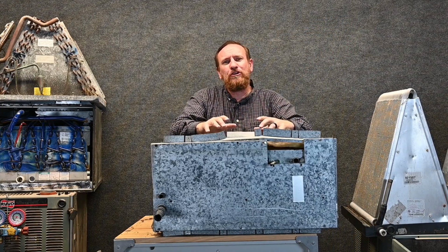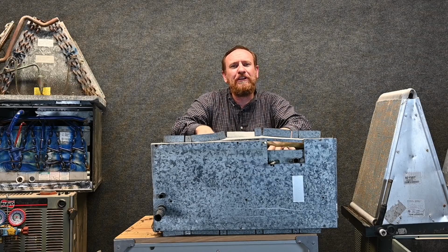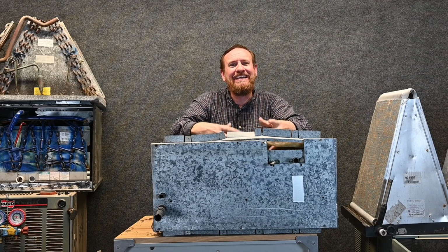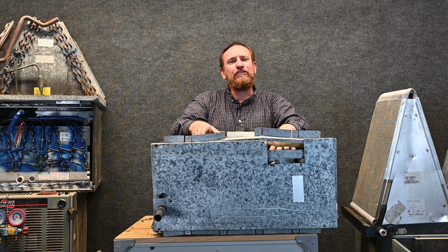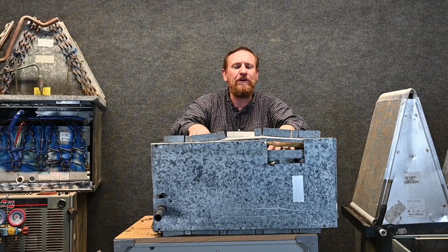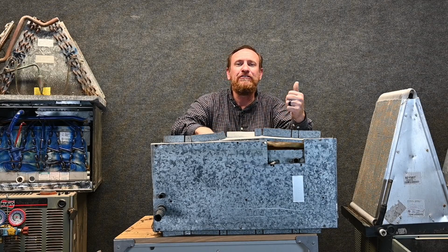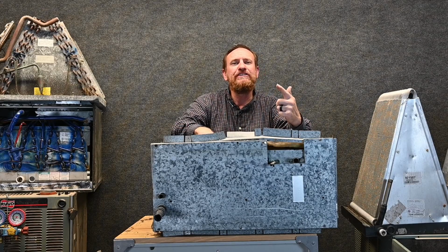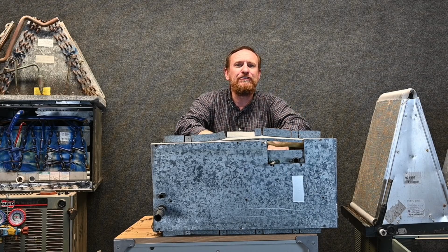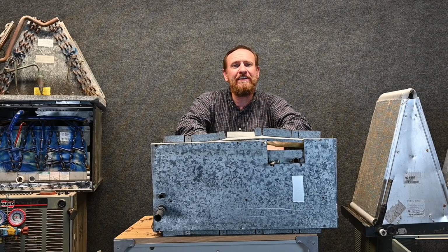Let's just do a quick little recap. The refrigerant is boiling from a liquid to vapor. That's latent heat, that's saturation. And then the refrigerant is superheated, the last part of that evaporator coil. On the air side, we want to dehumidify the air, which is latent heat, and cool the air, which is sensible heat. We want to make sure that the evaporator coil is not dirty because that slows heat transfer, and also it blocks airflow. So checking the condition of that evaporator coil is very, very important.